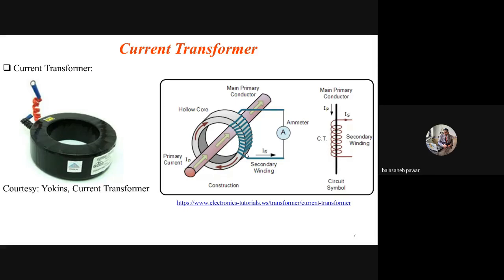Okay, so remember, generally a secondary coil with open terminals is not preferred. Otherwise there will be saturation across the secondary whenever there is a non-zero flow of primary current. So across the secondary, mostly one small resistor is connected. That means here the ammeter is shown. Instead of an ammeter, just one simple small-value resistor is connected, and then across that resistor the voltage drop is measured.